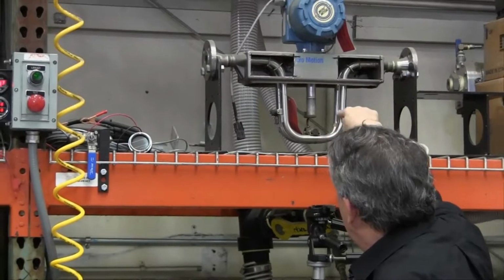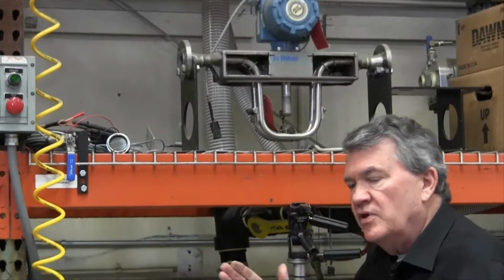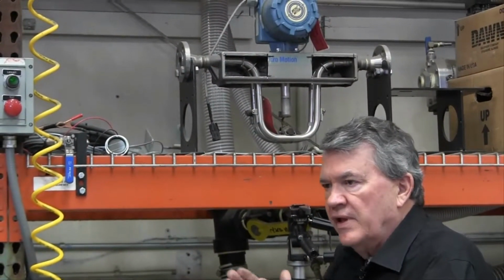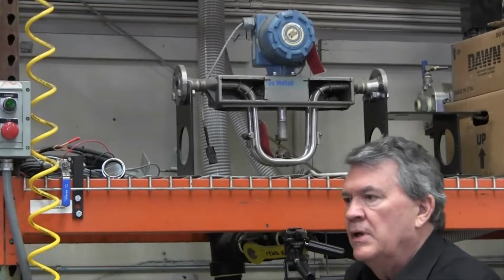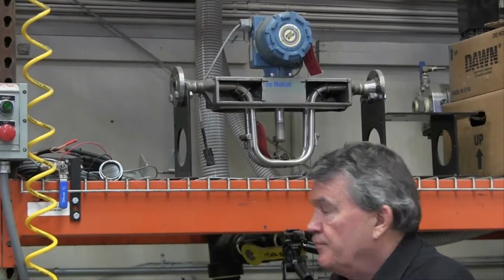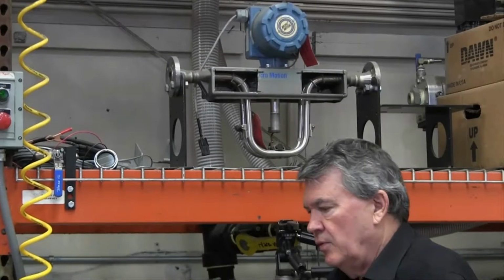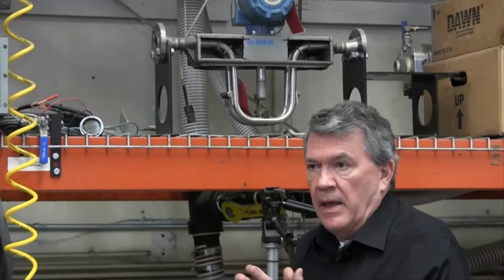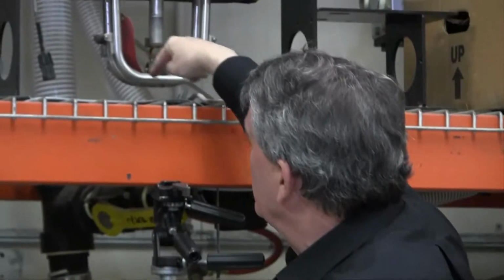As it comes back around, it changes the vibration of those tubes, and so as it gets heavier and heavier, there's more flow, you get a frequency change. And the frequencies we're dealing with on this particular unit is at about 1,000 hertz. We get about 1,000 hertz, we get 350 pounds per minute flowing through here. So very important to understand that this is not a turbine flow meter, it's a mass flow meter.